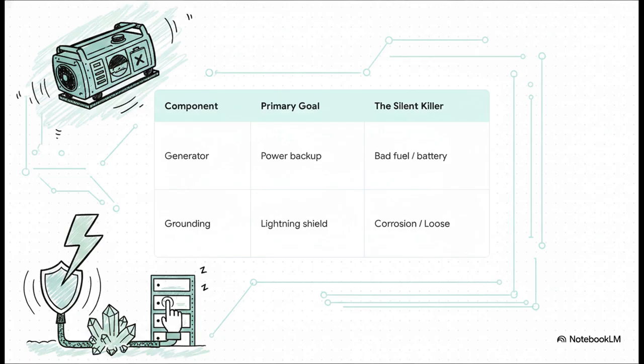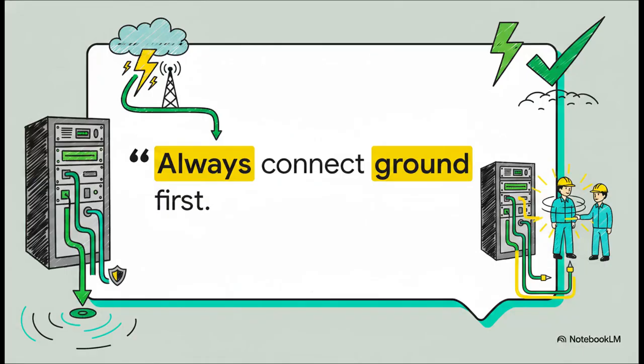So, if you take nothing else away from this part, remember this pro tip. Always connect the ground first. You have to treat the ground wire as a literal life safety issue, making it the very first wire you attach and the absolute last one you ever disconnect. It's the single most important wire in the entire site because it guarantees that if there's a static charge or a massive lightning strike, the equipment and the human being standing next to it are totally protected.